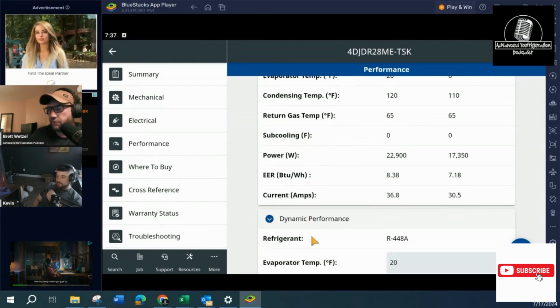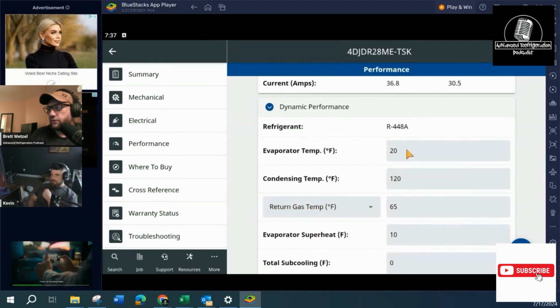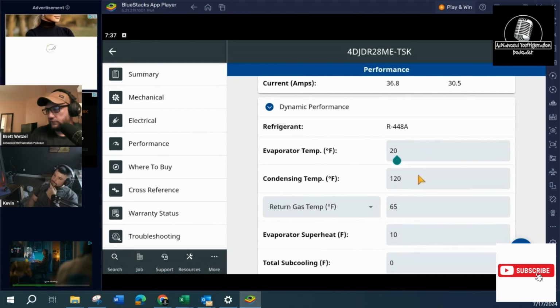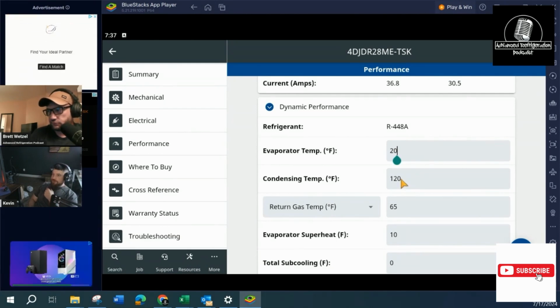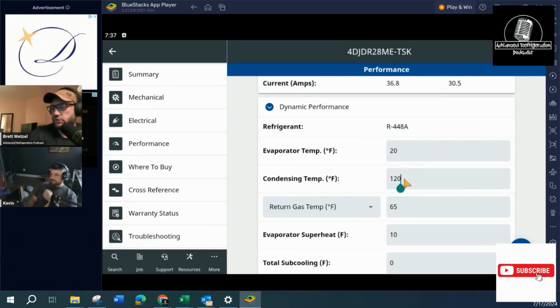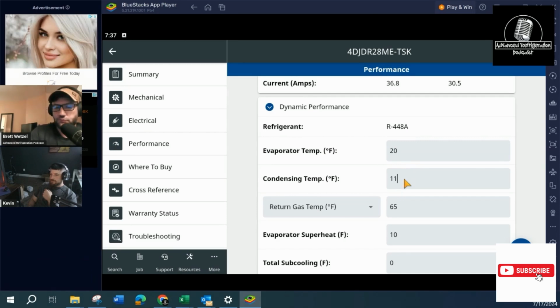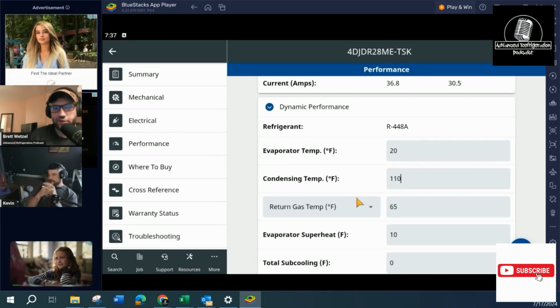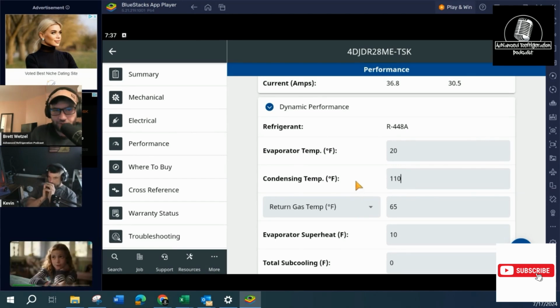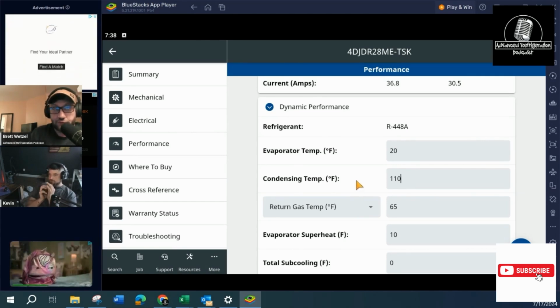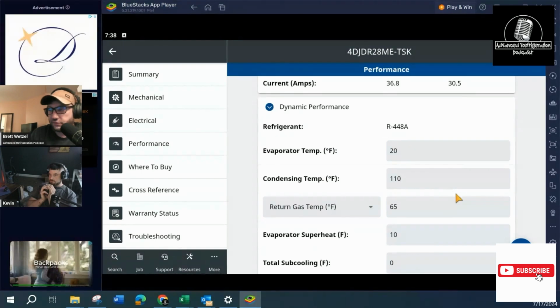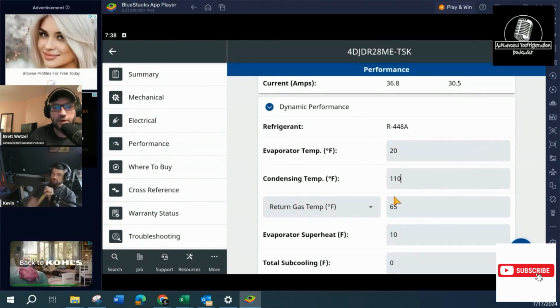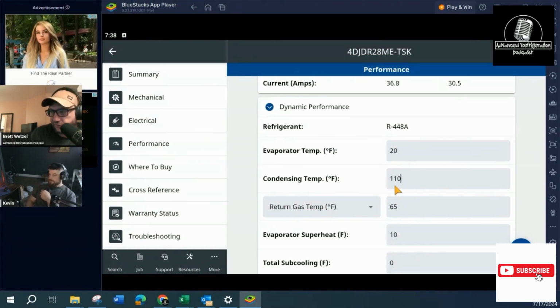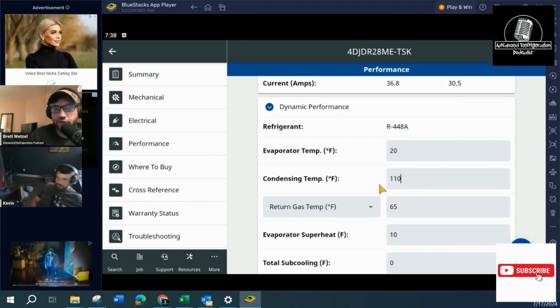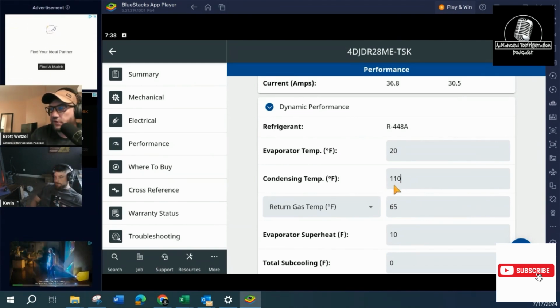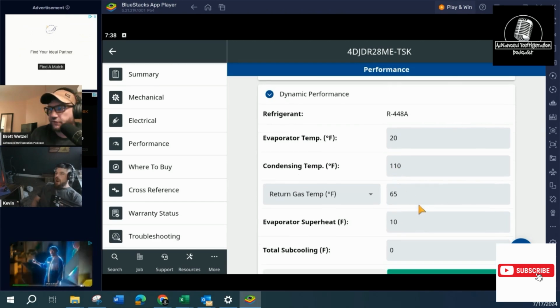So here, if we go to dynamic performance, let's first start off and do the same exact thing. Run the same exact test. 110? Yeah. Typically if you have a medium temp rack, those have anywhere from a 12 to 15, or 12 to 18 degree delta T on the condenser. I always want to say gas cooler, from here on out for everything. But anyway, for the condenser, that's essentially 110. Then minus 15 would be 95 degrees. So this would simulate a 95 degree day.